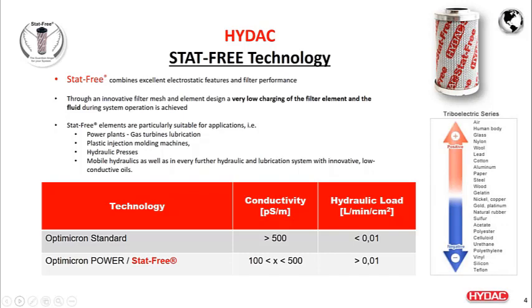The charge cannot jump from one to another because the dielectric constant was strong enough. So when HYDAC developed the stat-free elements, we started successfully employing them in power plants where there is a very high hydraulic load going into the system, and very low conductivity.